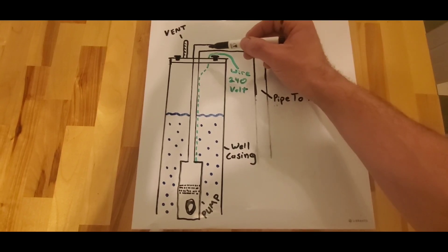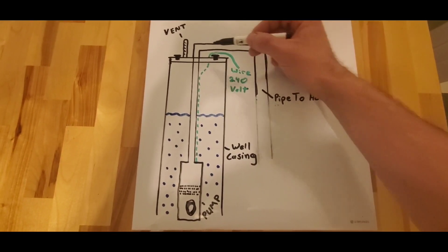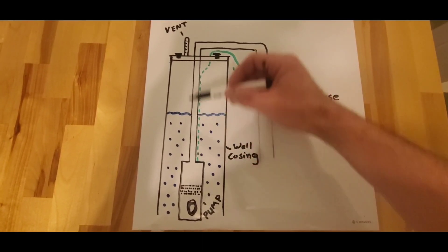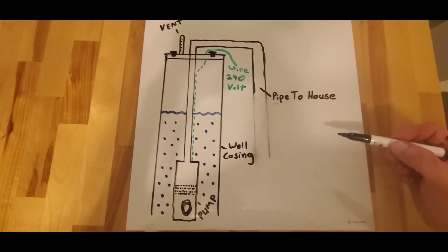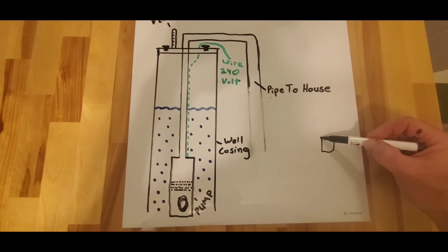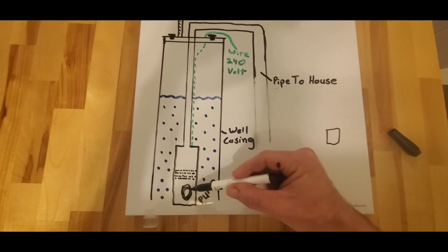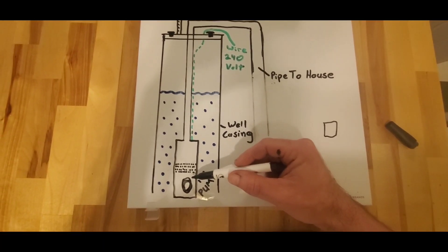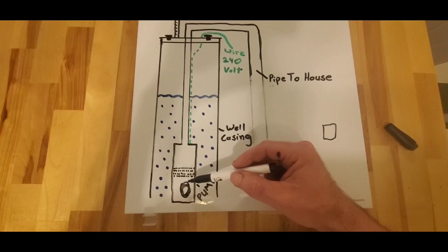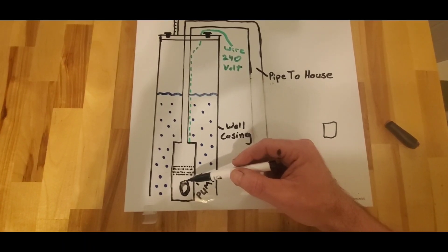Because the ice obstruction in this pipe here will not allow it to satisfy the pressure switch over here at the house, what happens is the electric motor becomes extremely hot, and it will eventually turn itself off on a thermal overload. Now that's upwards of 200 degrees.